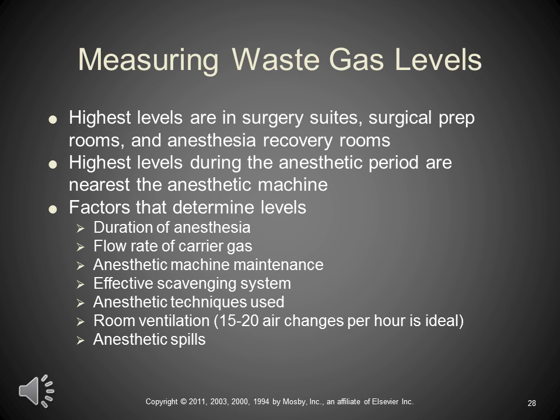The highest levels of waste anesthetic gases are generally going to be in the surgical suites, in the prep areas, and in the recovery rooms, because that's where the anesthetics are. The highest levels will be during the anesthetic period, and they're going to be nearest the anesthetic machine, because that's where all the anesthetic is.